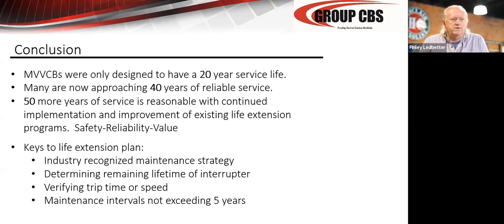But if you use the pinning test, you would have picked that up at the last maintenance cycle, and you would have known not to put it back into service, because the pinning principle will tell you, do you have 2 years, 5 years, 10 years, or 20 years service life left in the interrupter? That interrupter would have come back and told you at the last maintenance cycle to replace it. So it essentially would have solved the problem for you.